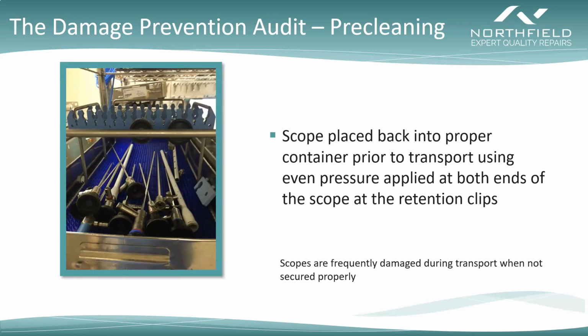We also want to make sure that the scopes are being placed back into their proper containers prior to transport, and keep in mind to continue to use even pressure applied to both ends of the scope at those retention clips, just exactly like we talked about at the very beginning, that if we are pressing down just in the middle, it's going to cause that flexion in that shaft, and that's how those glass rods get broken.